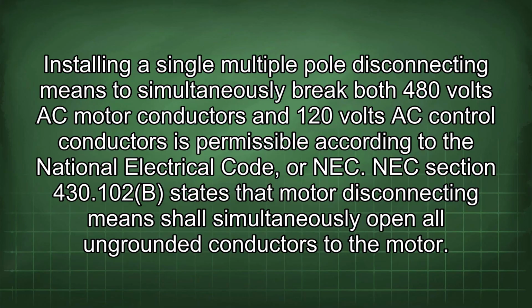Installing a single multiple pole disconnecting means to simultaneously break both 480 volts AC motor conductors and 120 volts AC control conductors is permissible according to the National Electrical Code, or NEC. NEC section 430.102(B) states that motor disconnecting means shall simultaneously open all ungrounded conductors to the motor.